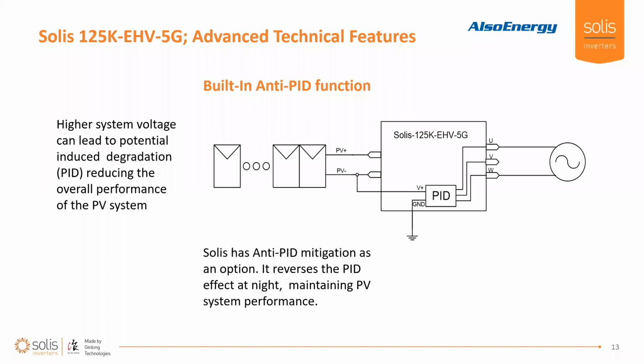It's just part of physics that as we up the voltage in these PV systems, the PV modules can get more susceptible to this induced degradation. Solis has been working on this for a while and now has this anti-PID mitigation as an option. Essentially it's reversing the PID effect at night, and you can really maintain the performance of all your PV modules within the array.